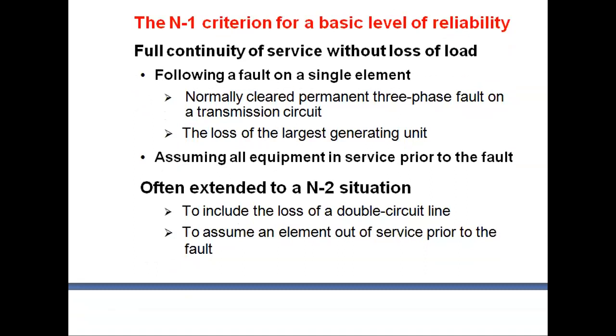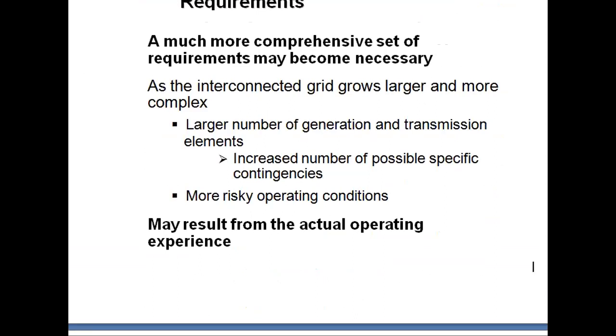If an N2 situation occurs, that means to include the loss of a double circuit line, assuming an element is out of service prior to the fault. Additional performance requirements state that a much more comprehensive set of requirements may become necessary as the interconnected grid grows larger and more complex, with a larger number of generation and transmission elements, an increasing number of possible specific conditions, and more risky operating conditions resulting from actual operating experience.